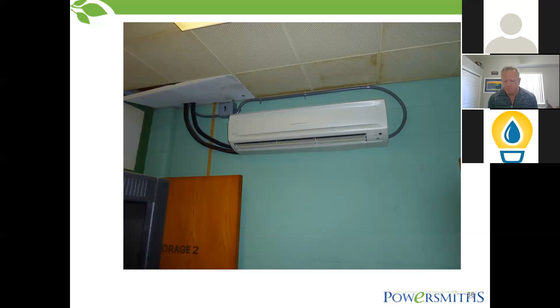And I said, how's the new ones coming along? He goes, oh man, it's great. He says it cost about $9,000 per electrical room in every school, and in some schools there's 10, 15 electrical rooms. It costs about $9,000 per electrical room to put a dedicated DX system to cool the transformer. Now that we've replaced it, I could have just replaced the transformer, a $4,000 transformer, and not had the DX system in there. He said it makes total sense why they didn't look down this path, because a lot of people just assume transformers are supposed to be hot and humming. It's just not supposed to be like that.